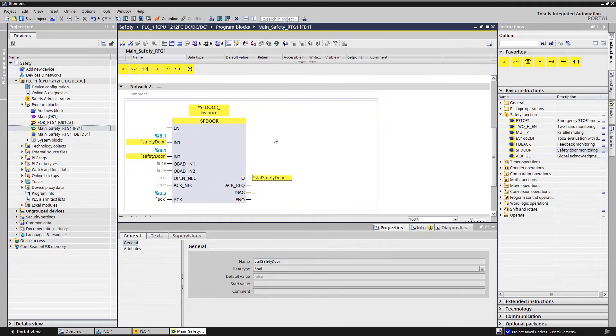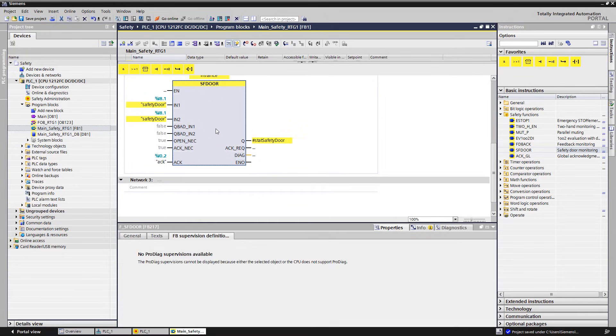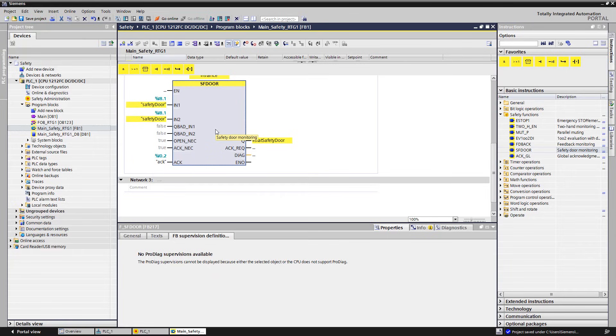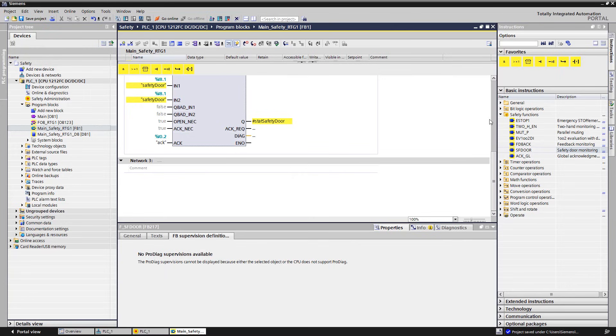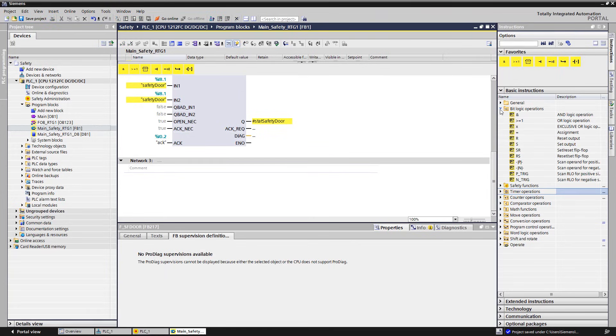We now have executed the evaluation of the control devices and have to carry out the logic for the safety shutdown of the starters. The safety shutdown logic should be as follows: When the start button is activated, it is turned on safely. When the emergency stop button is actuated, when the safety door is opened, or when the stop button is activated, it is switched off safely. This logic is implemented by the relevant interconnection of the blocks.